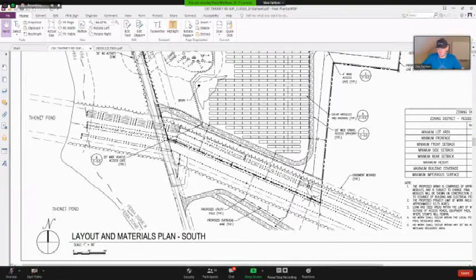Similar to Charge Pond, where we were not right on, but pretty close to a public way, I was very willing to put this equipment on the ground. As a general design criteria, we try not to keep the stuff on the ground. I think there's just more that can go wrong. And in an environment like this that has 2 high voltage transmission lines as well as 2 medium voltage distribution lines already in that right of way, I personally didn't feel like the addition of those 8 or 10 poles was material. But obviously, as we've proved before, we can put this equipment on the ground if it's really important, but my preference is to keep it on the poles. So I'd certainly defer to the board. If you would like to urge us one way or another, we're happy to comply.